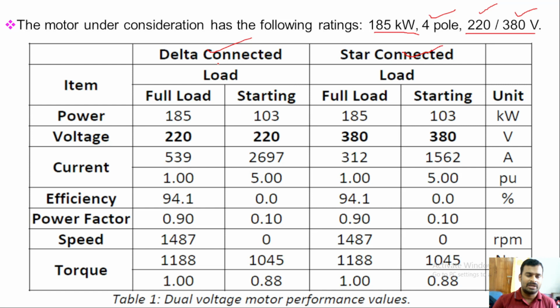In that case, if you connect appropriately, the power will be 185 in both at full load condition, and the voltage 220, 380, and the current you can see here 539, 312, and the starting current is almost 500% of the full load current. It is almost okay, it is not an exact value. The efficiency remains the same for both star and delta configuration, 94.1, and the speed remains the same, 1487 and 1487. Torque produced is also the same at full load condition, 1188, 1188.